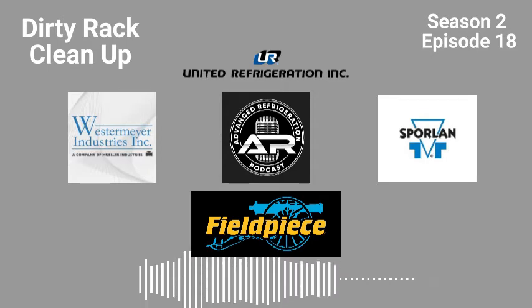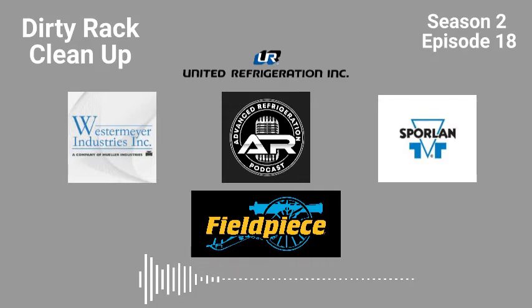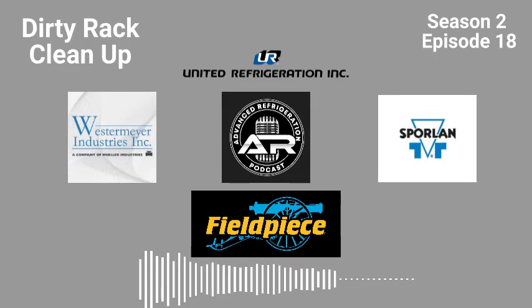Yeah. Sporlan actually makes a new kit that goes inside of the dryer shells. So you could buy the replacement guts. Change your dryer shells while you buy the replacement guts. I think it's a 1 or 5 micron filter that goes over that. The new style screen is that long shaft, where the whole shaft is the screen, not just the end plate. So you could buy a filter that goes over that screen. Dude, it catches everything. But it blocks up quick as hell. We had a rack. Good. That's what we want. We want it to block up quick. I mean, no, we want it to catch everything.